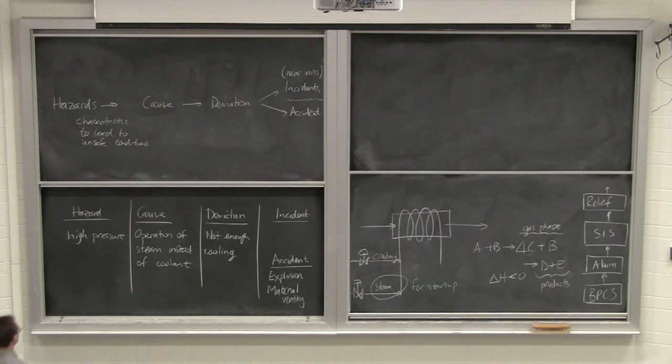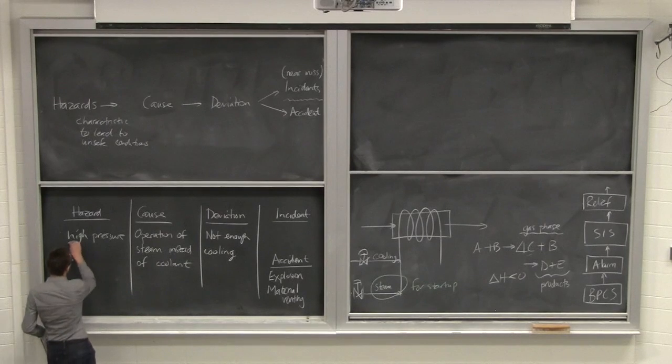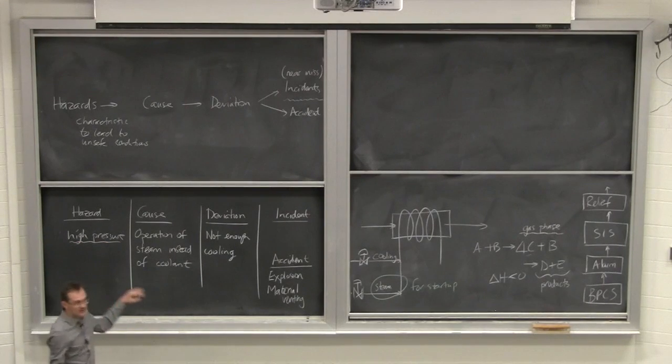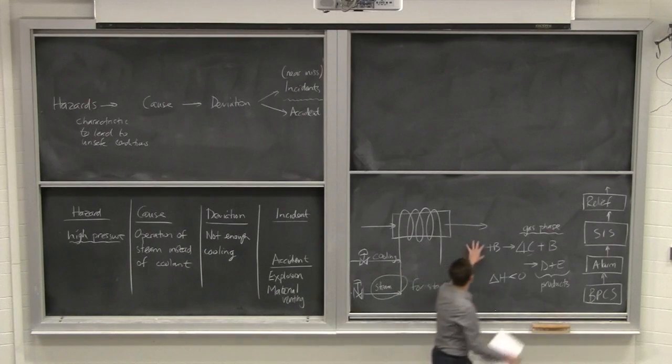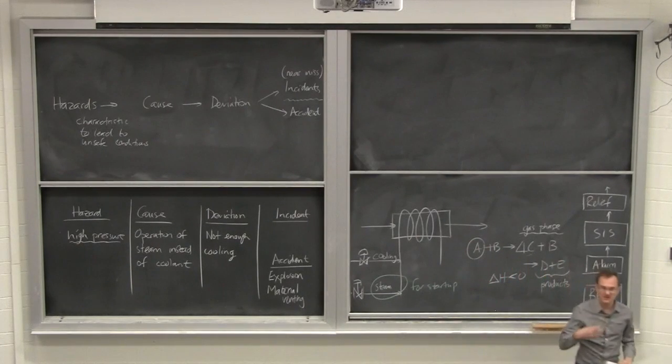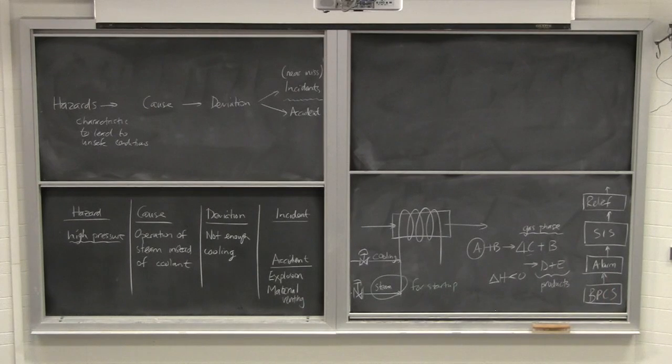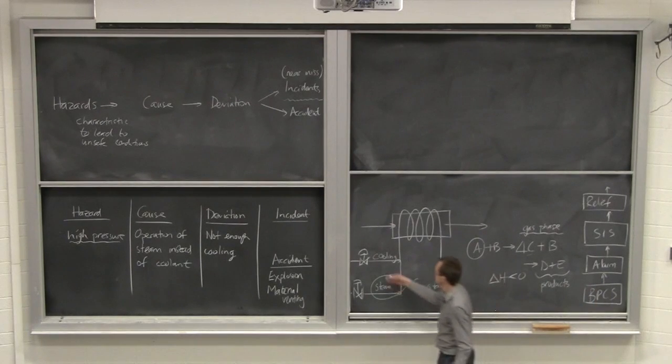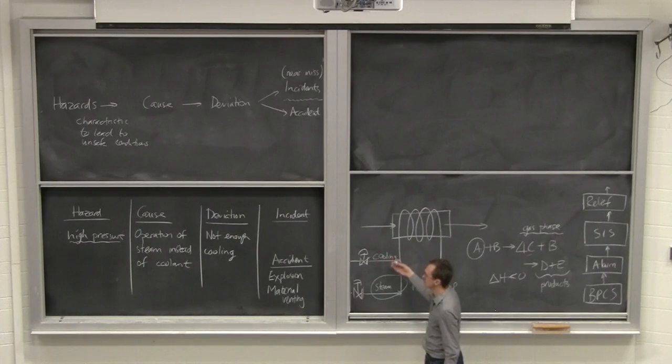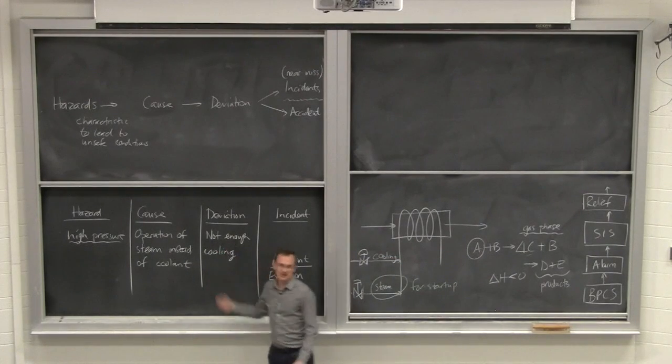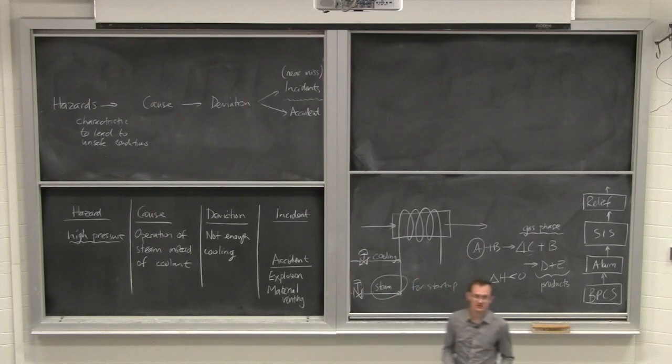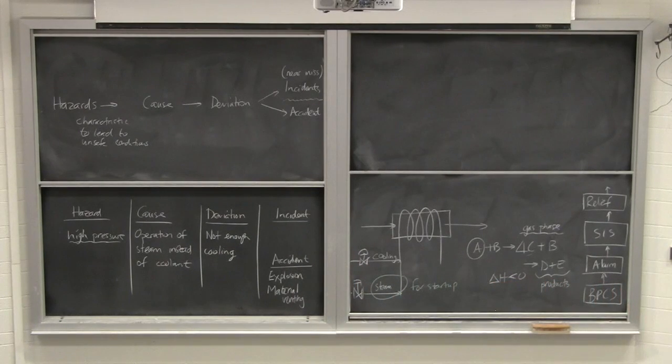Okay, now if you look at this hazard, it could be caused here by operation of steam instead of coolant, but it might also, the same sequence of events could have occurred by using a concentration of A that was higher than we normally do. Okay, so same way, same sequence of events just by using a higher concentration of reactants. Okay, and it might not even be the steam being opened, it might simply be the cooling flow rates dropping. So coolant flow drops, and again, the same sequence of deviations and causes occur.